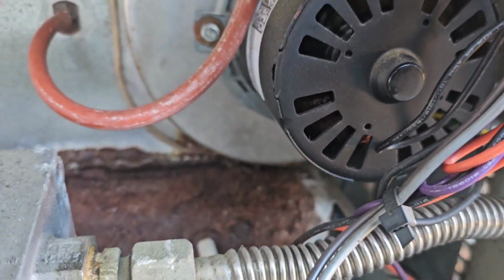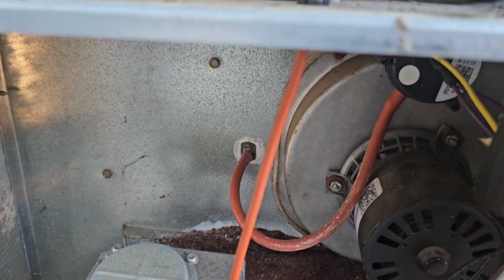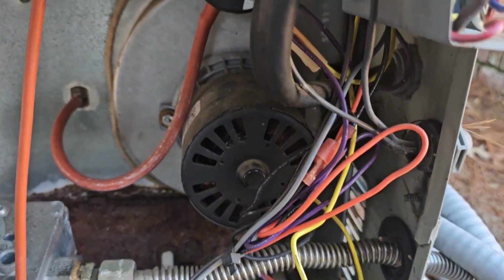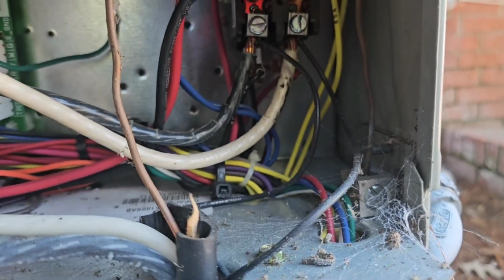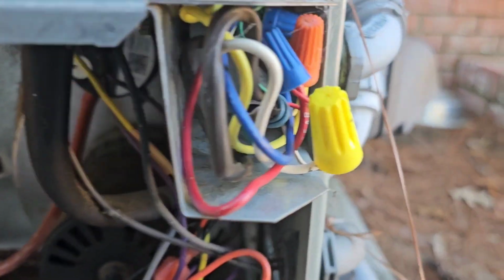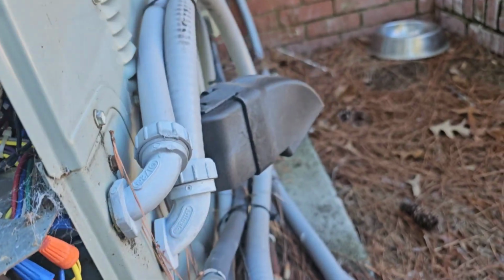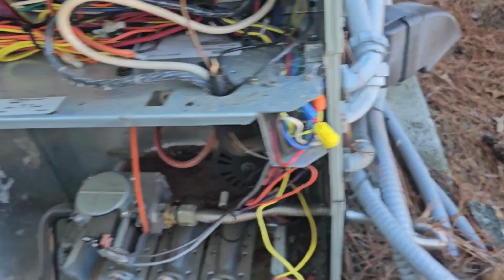The inducer draft motor ain't even trying to run. I don't think this is a dual fuel. It's possible this is a dual fuel, unless the thermostat wire is one of the wires going in. Ah, yeah, that's what it is. Okay, all right, so we just got a gas pack.